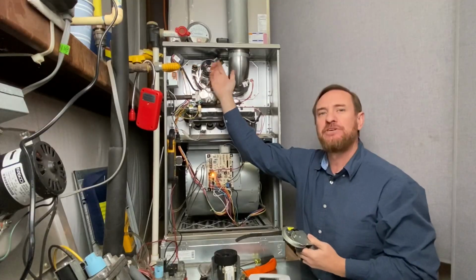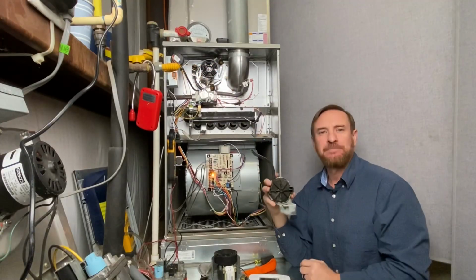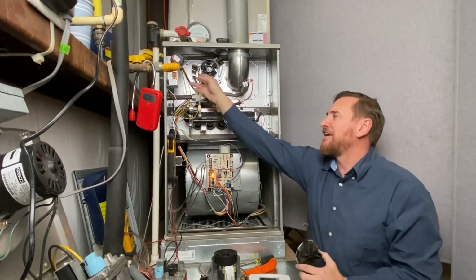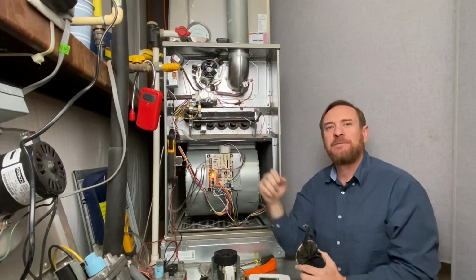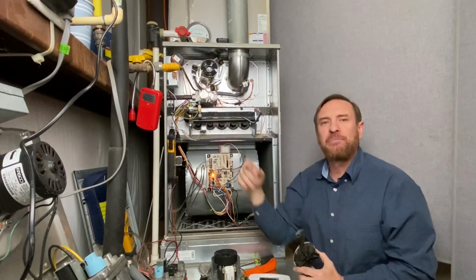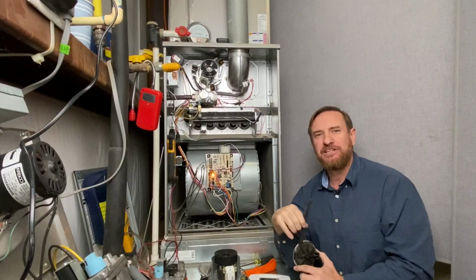It's going to pull a vacuum. You can see what the vacuum is. Fieldpiece makes a really nice little meter that you can actually disconnect the hose entirely, hook it up to the instrument, hook your wires up to the pressure switch, and it tests that switch for you individually.